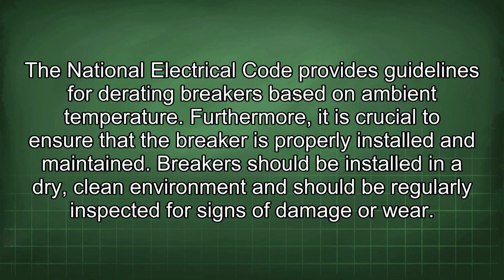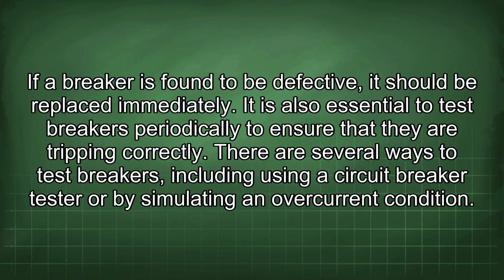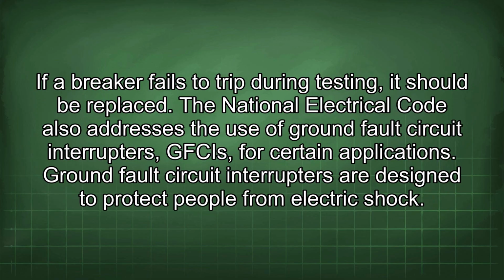Furthermore, it is crucial to ensure that the breaker is properly installed and maintained. Breakers should be installed in a dry, clean environment and should be regularly inspected for signs of damage or wear. If a breaker is found to be defective, it should be replaced immediately. It is also essential to test breakers periodically to ensure that they are tripping correctly. There are several ways to test breakers, including using a circuit breaker tester or by simulating an overcurrent condition. If a breaker fails to trip during testing, it should be replaced.